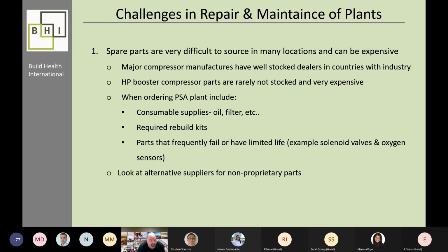When ordering a PSA plant, it's very important to include consumable supplies. The compressors require special oil from the manufacturers, which is almost impossible to come by in many settings, so various types of motor oil end up being used, which degrades the life of the compressor. There are multiple filters on these units that need to be changed regularly, and especially the high pressure compressors require rebuild kits every 8,000 hours, usually every 9 or 10 months.